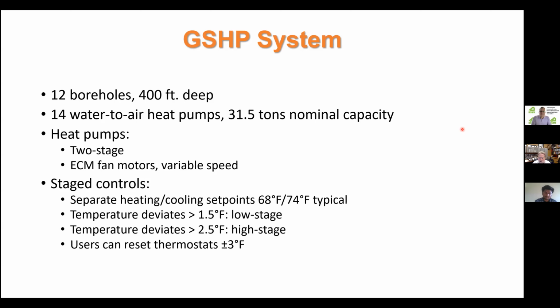And the heat pumps were, when they were installed, I think pretty much state of the art. They were 2-stage units with ECM fan motors and variable speed for the fan motors, although they operated at standard set points for each stage, or standard flow rates for each stage. The controls were staged. So first of all, there were heating and cooling set points. 68 and 74 were typical, though users could reset them. But unlike the VRF system, which was trying to maintain within 1 degree of set point, the ground source heat pump system could float between the heating and cooling set point. And if the temperature was exceeded by, if I remember right, 1.5 degrees, we put on the low stage, cooling or heating came on. If it was more than 2.5, the high stage, heating or cooling came on.